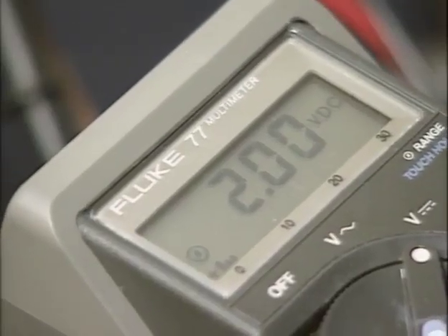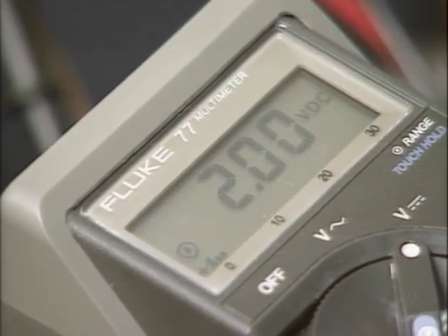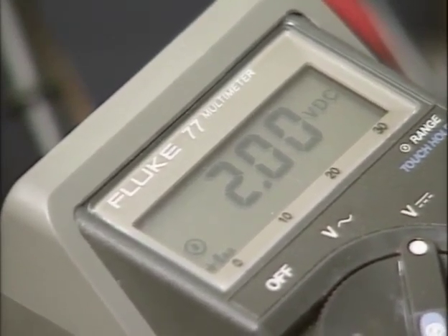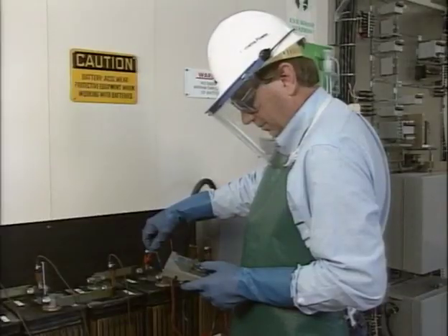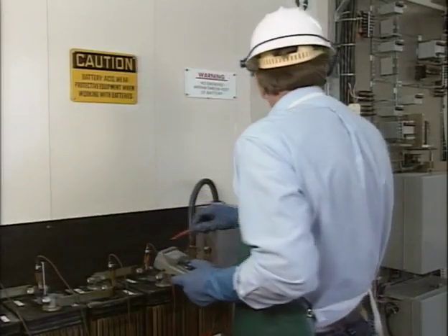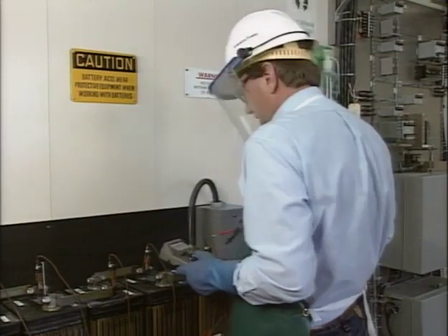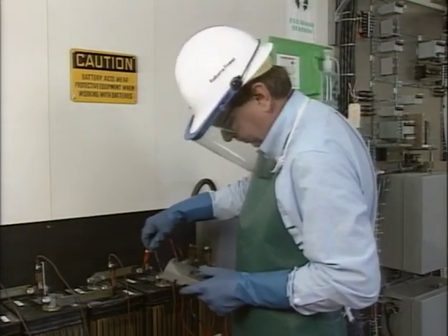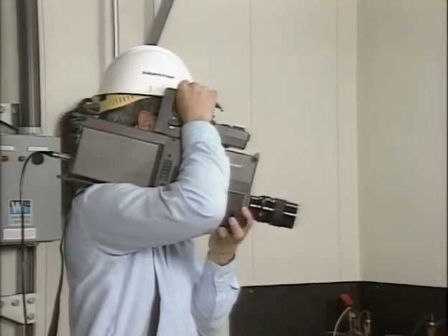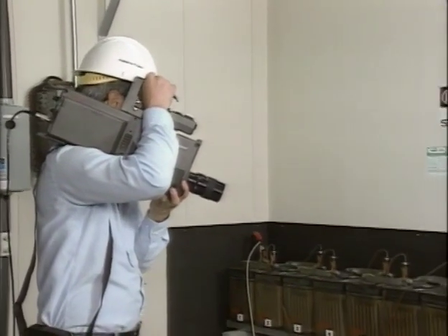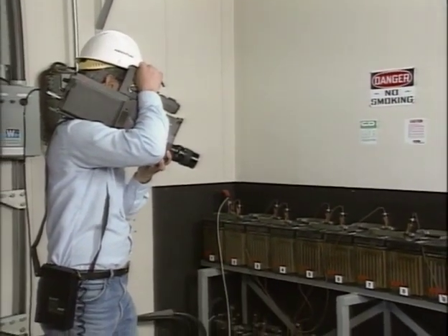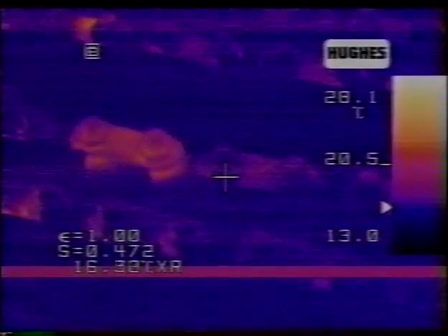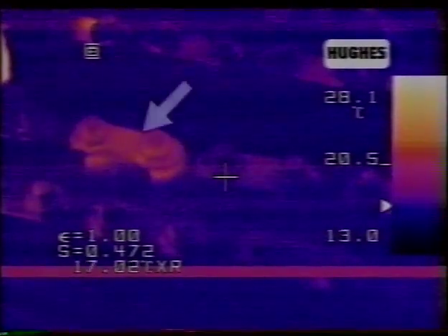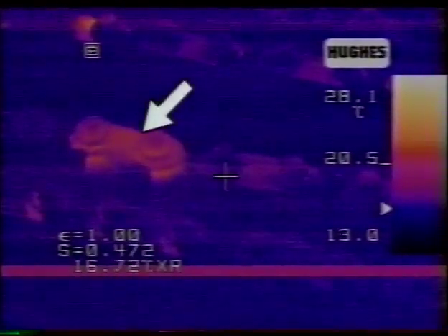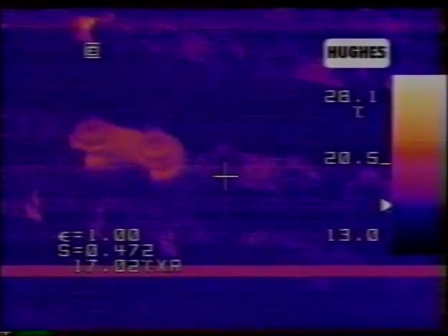If this voltage is similar to the other cell voltage readings, the excessive voltage drop is caused by the intercell connection. Poor intercell connections can cause heating. For this reason, poor connections need to be closely watched for excessive heating throughout the rest of the test. Intercell connector heating can be checked in a number of ways. In this example, heating is monitored using an infrared camera. When properly used, an infrared camera will show any hot battery connections. These connections will need to be cleaned and checked for high resistance before the battery is put back into service.